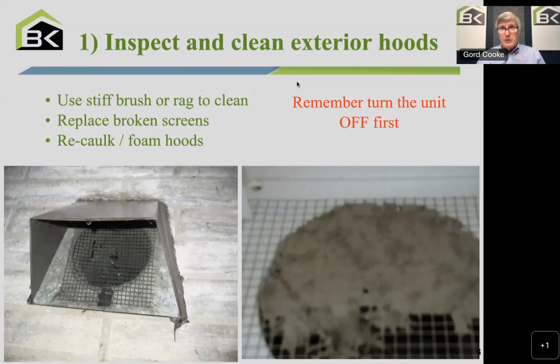Some people think, well, I'll put a fly screen on there, a very fine mesh like a screening. The problem with that is they're too restrictive and they need very, very regular maintenance. So you'd have to check those once a month. These screens, typically these 1/4-inch mesh screens, you're talking about once every 3 to 4 months, and in particular seasons, right? In the fall, remember I mentioned the smoke detector right around this time of year. Boy, you might expect there to be leaves. In the spring, it might be pollen and so on. That's caked it up. The dandelion seeds and so on might be clogging this up. So 3 times a year.